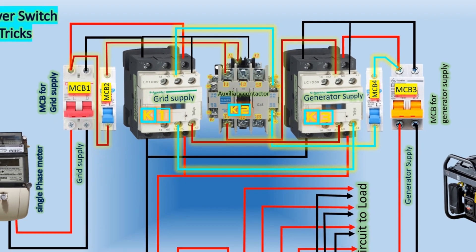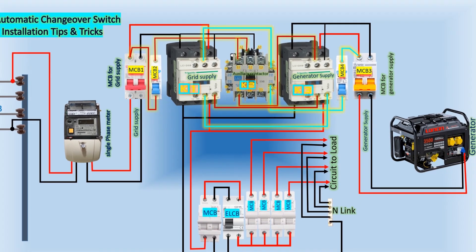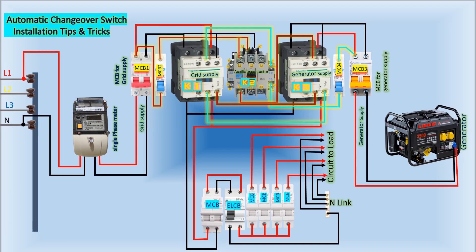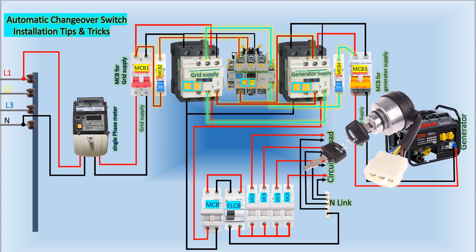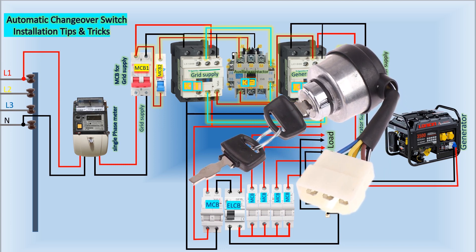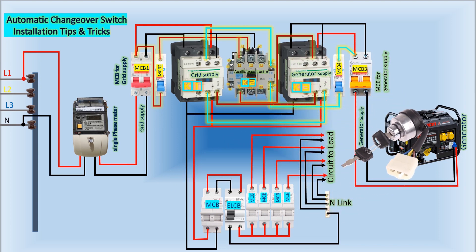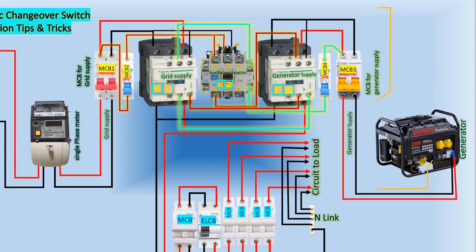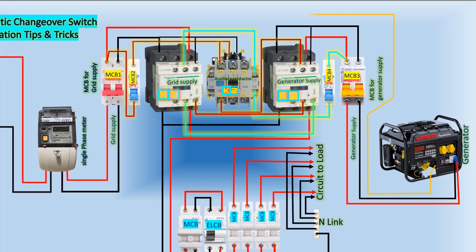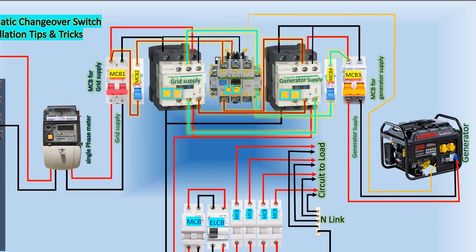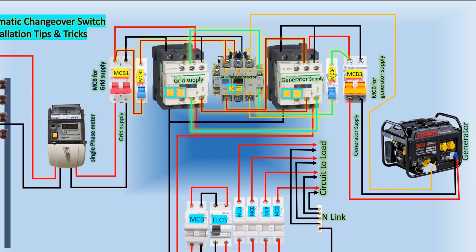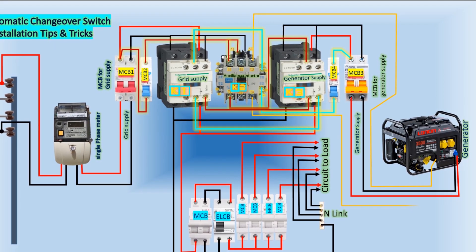If you want the generator to stop automatically, you need to locate the ignition wire — the switch wire that, when touched with the generator body, causes the generator to stop. Typically, the ignition wire is either black or blue in color. To achieve automatic shutdown, locate this wire and connect another wire to it — in this case, we will use an orange wire. This wire is connected to the L3 terminal of contactor K2. From the T3 terminal of contactor K2, a wire is connected to the generator and linked with the generator body.